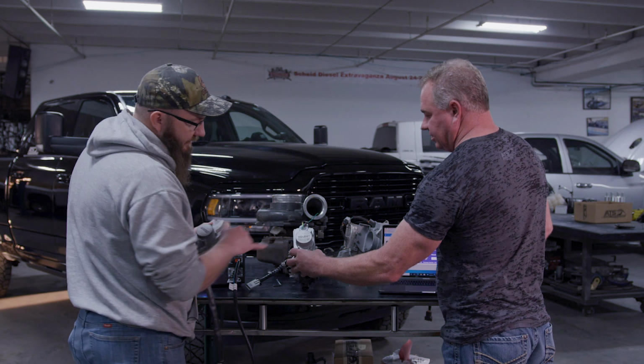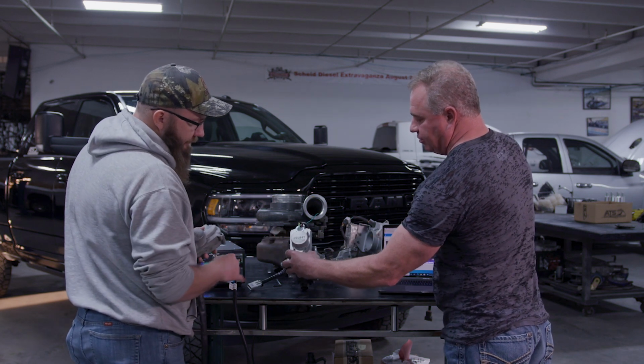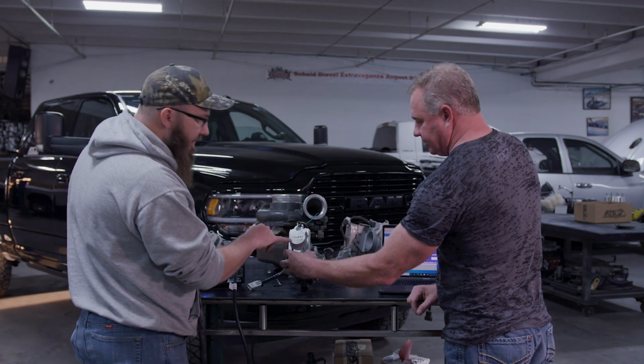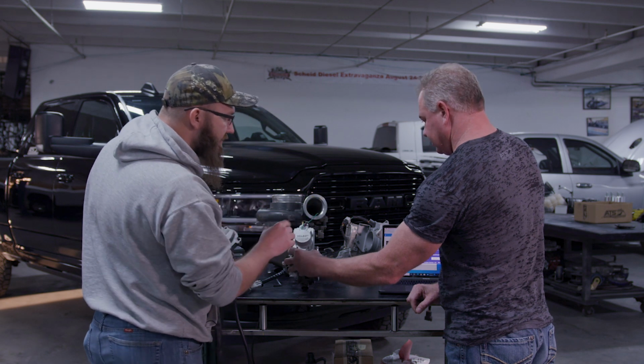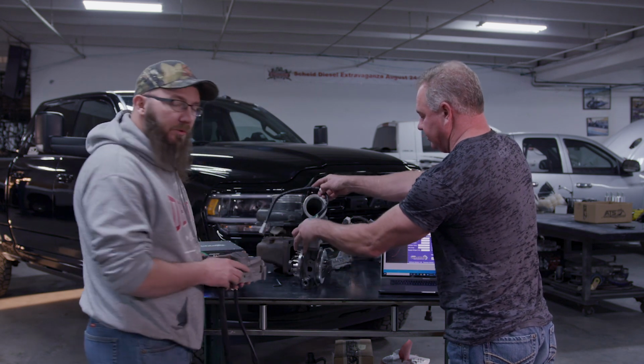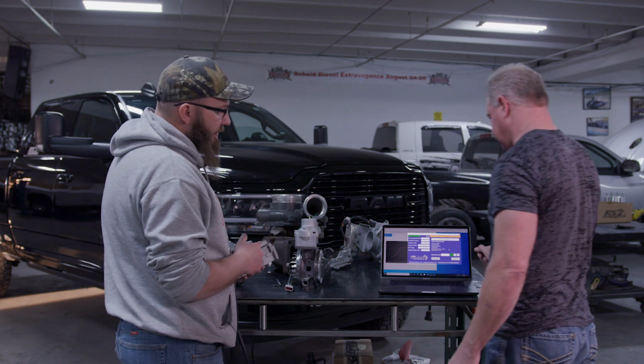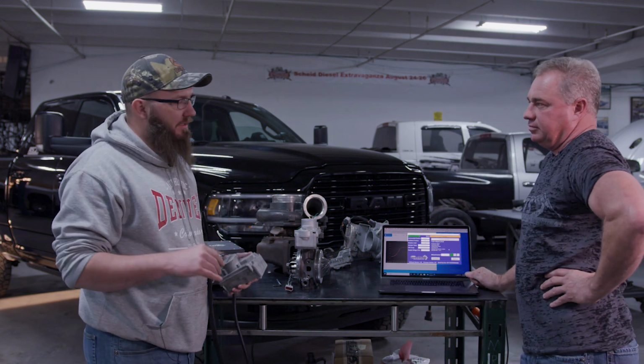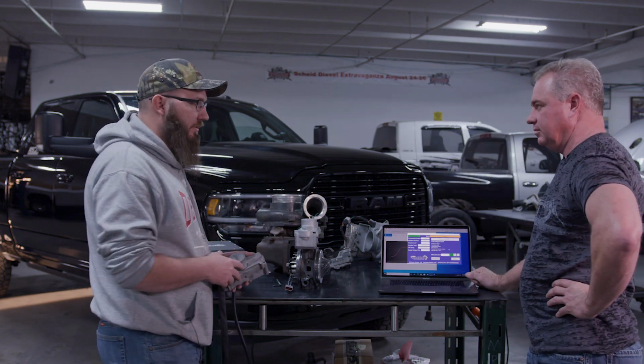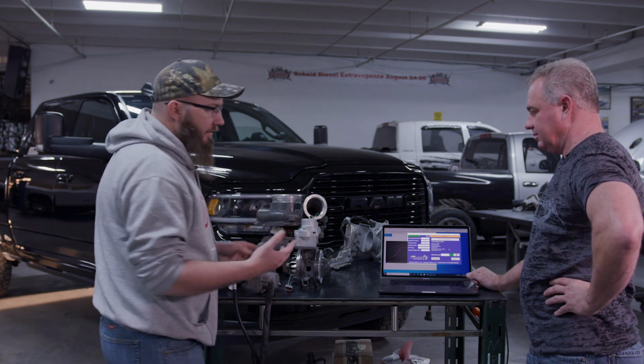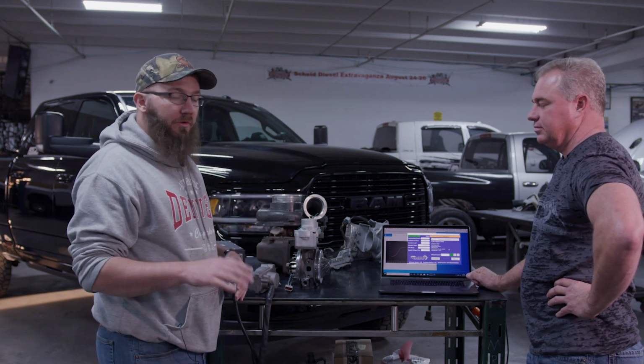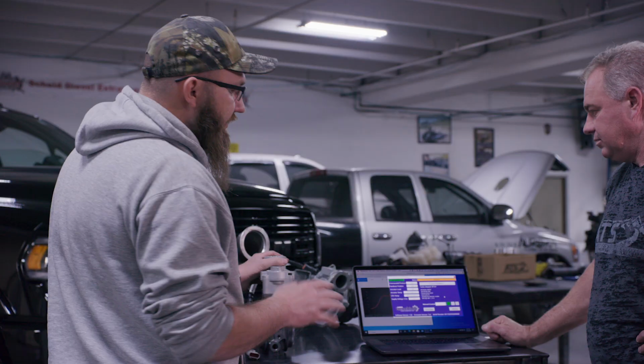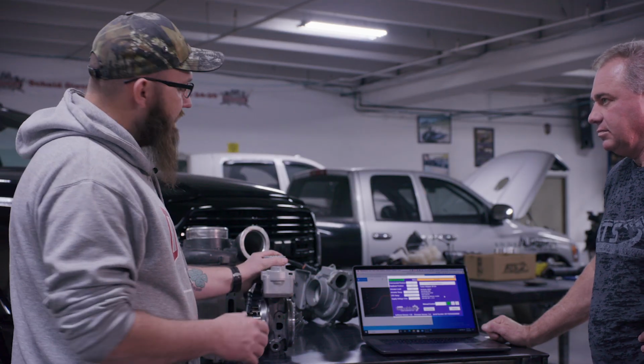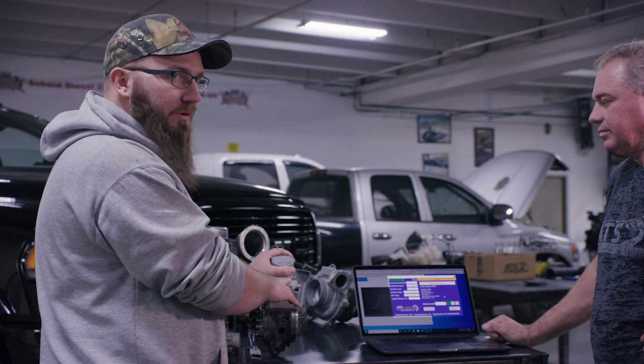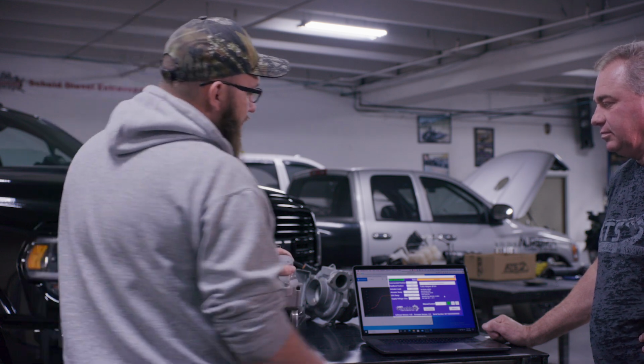In this case, this is like a brand new whole set, and you'll notice the number matches. So the number right here, are you on 3? So you're on 300, okay, so there's a difference between the 351 and 300. The control calibration is generally the same, with slight differences but nothing you really need to worry about. But on the serial number itself, that's really what makes a difference. On the 300, the serial number is written in hexadecimal, whereas on the 351 they were done in decimal, so just regular numbers.